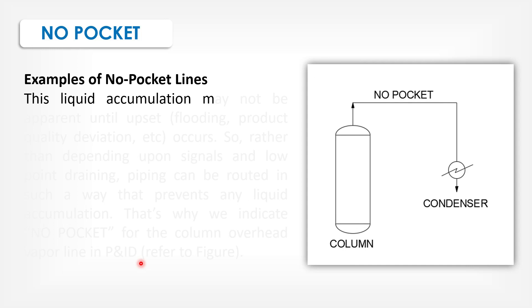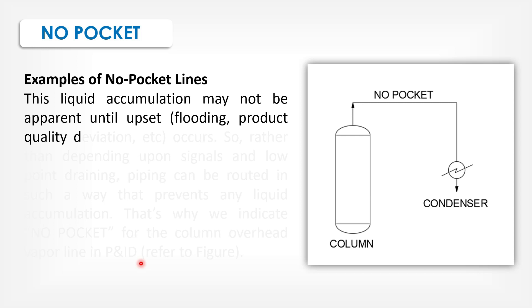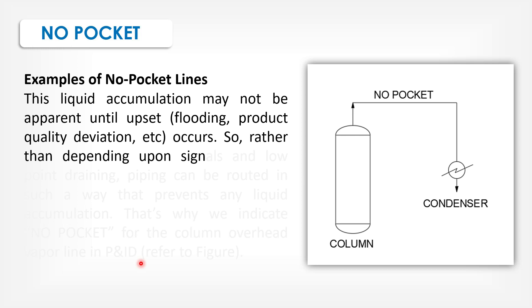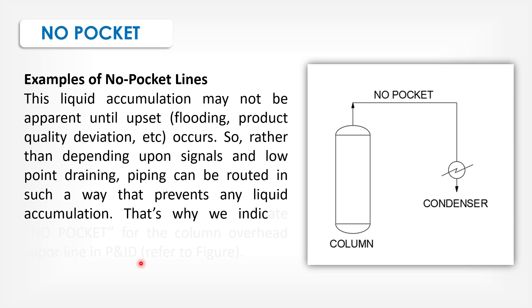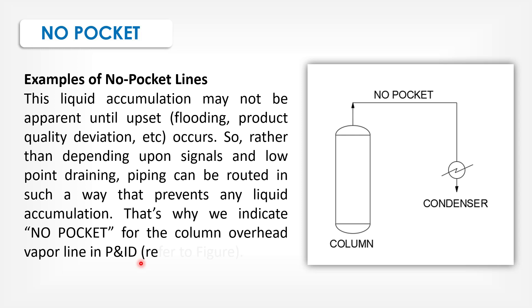This liquid accumulation may not be apparent until upset (flooding, product quality deviation, etc. Rather than depending upon signals and low point draining, piping can be routed in such a way that prevents any liquid accumulation. That's why we indicate no pocket for the column overhead vapor line in P&IDs.